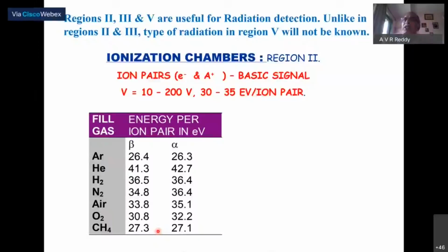So obviously the signal will be reduced, and then we have to correct for it. These are the ionization chamber detector materials. Normally ionization chambers are used to measure high dose radiation samples, and in some cases for spectrometric work.